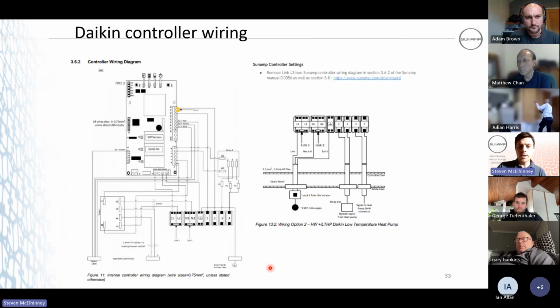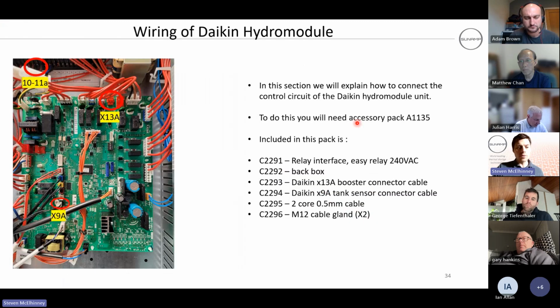So let's look at Daikin wiring. Booster signal wiring from the heat pump goes into terminals 1 and 2. Your control circuit is 3 and 4. So let's see how that looks.